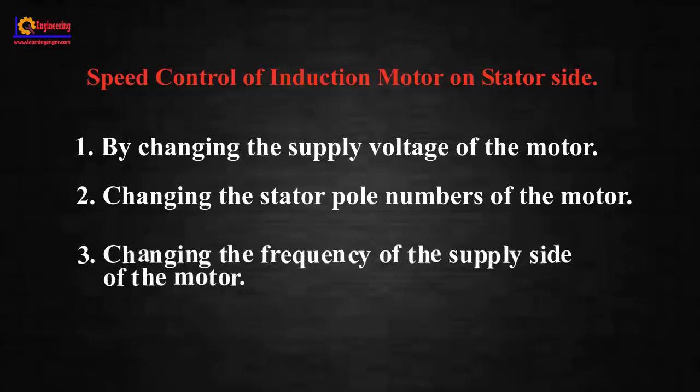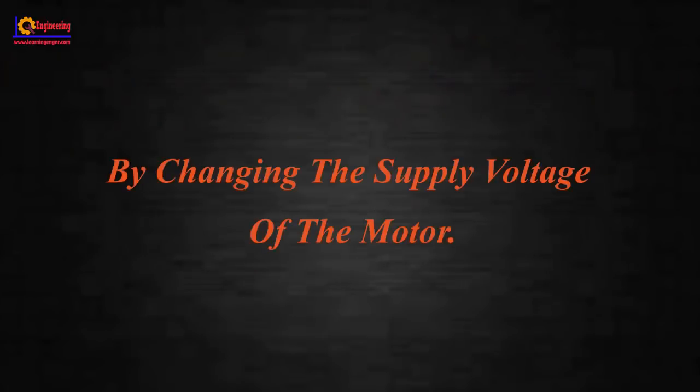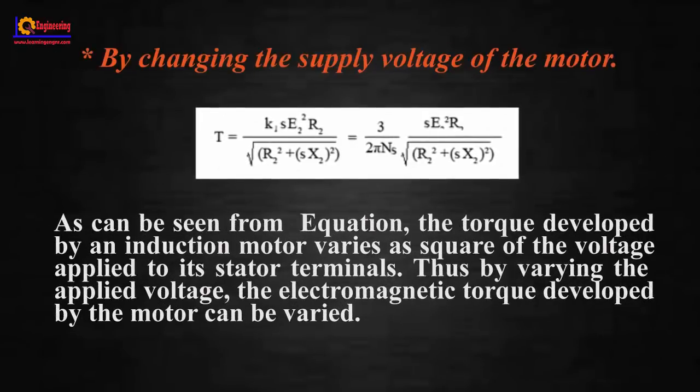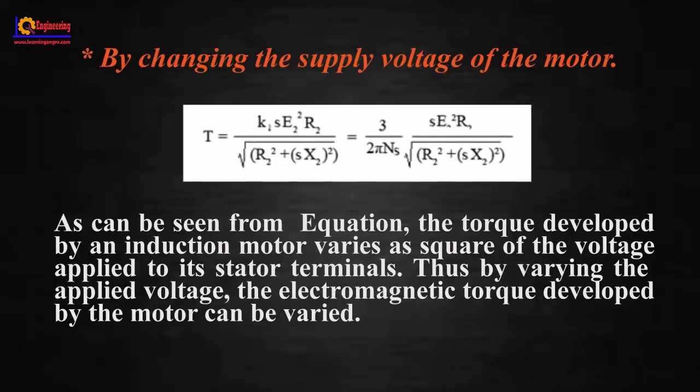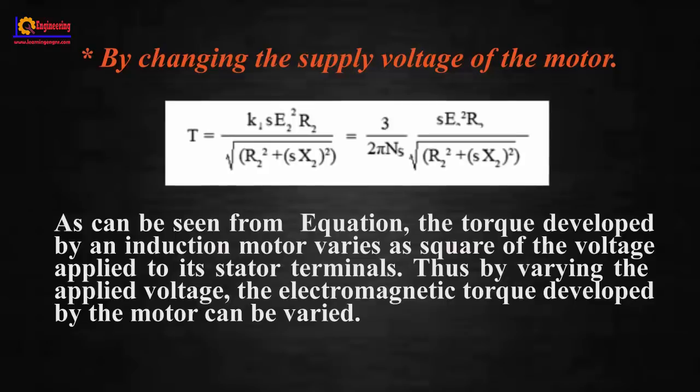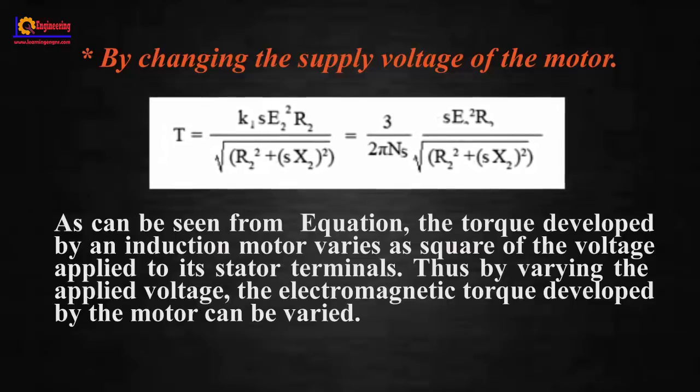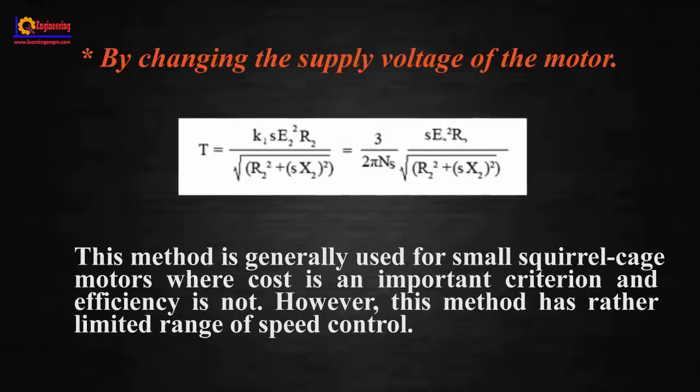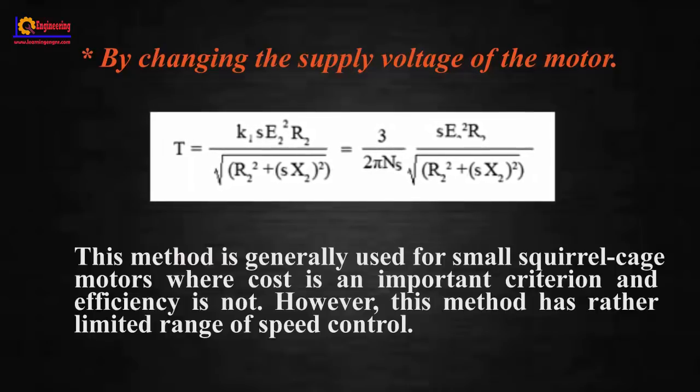By changing the supply voltage of the motor, as can be seen from the equation, the torque developed by an induction motor varies as square of the voltage applied to its stator terminals. Thus by varying the applied voltage, the electromagnetic torque can be varied. This method is generally used for small squirrel cage motors where cost is an important criterion and efficiency is not. However, this method has rather limited range of speed control.